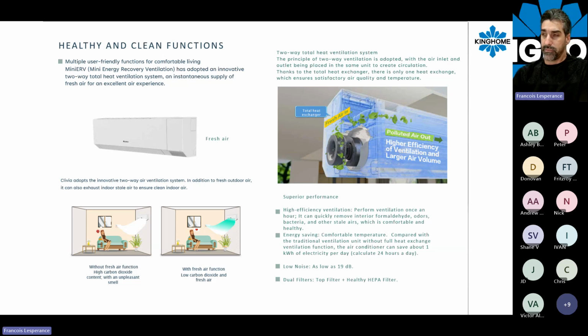The system is equipped with a heat exchanger. So there's a small total heat exchanger inside of this option, this Mini ERV, and then with another blower, we're able to push some fresh air in the room. And because it's matched with the high wall, the high wall will also be interconnected with the system, so it will perform as needed regarding the room temperature.